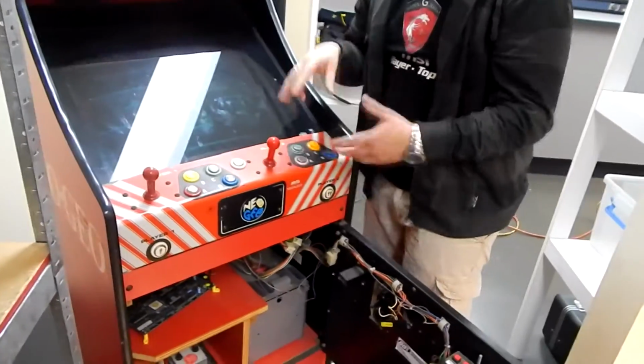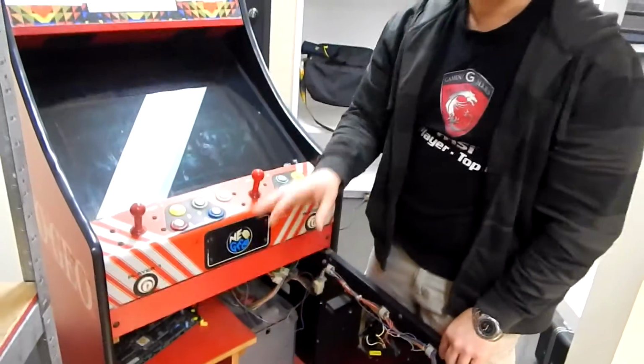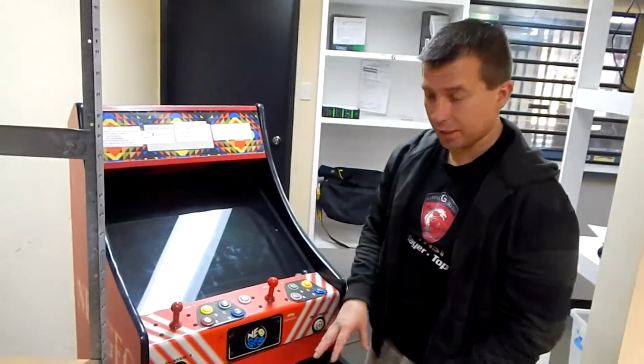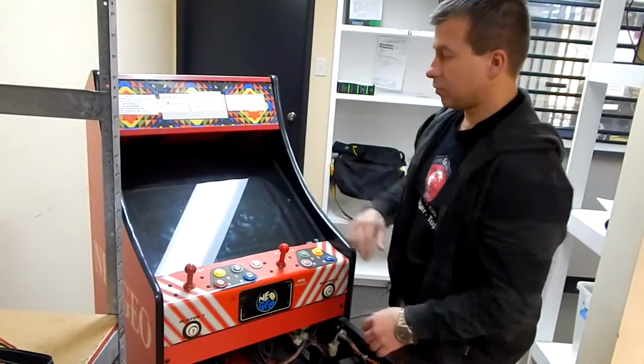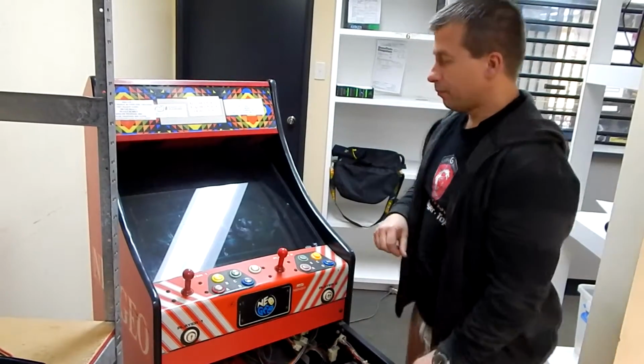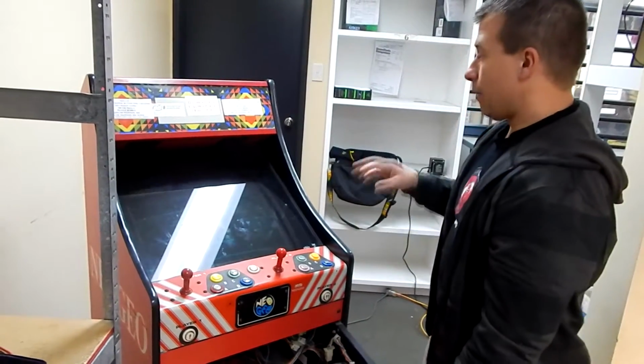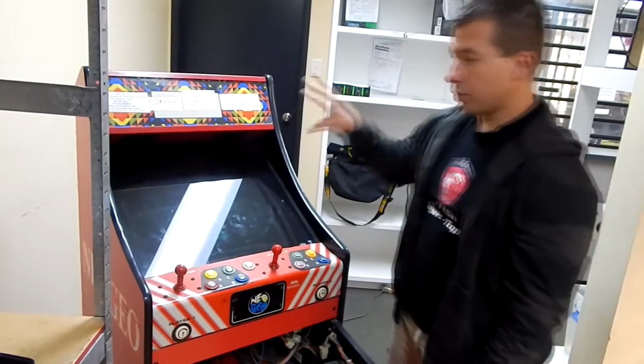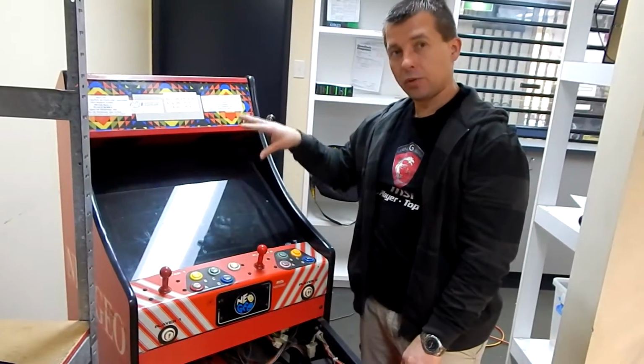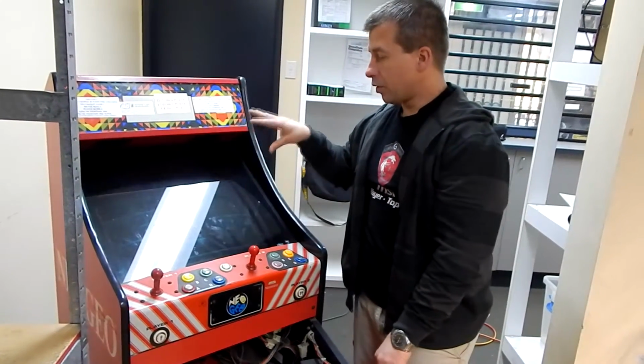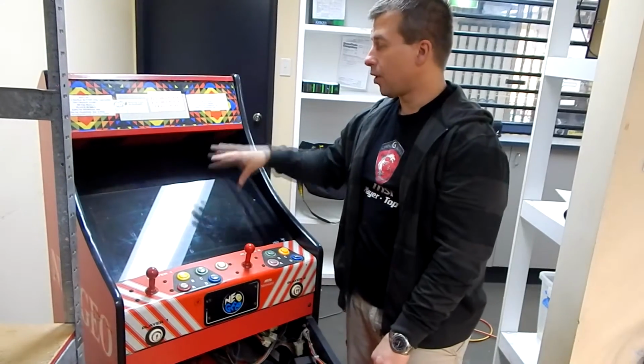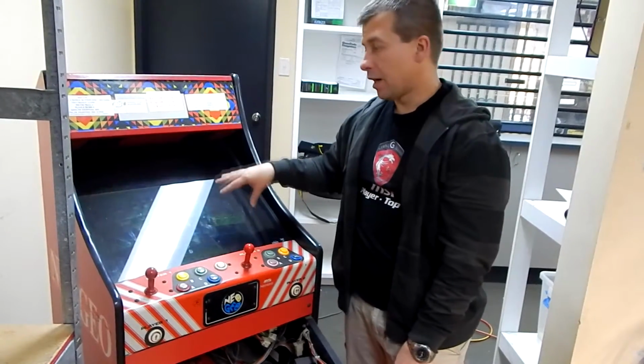We'll do the general run around, make sure the wiring's okay, make sure the voltages are set correctly, and that there's nothing in the back, cockroaches, rats, stuff like that. So what we'll do is turn this off, discharge the tube, and test the tube first. My suspicion is it's going to be the tube.